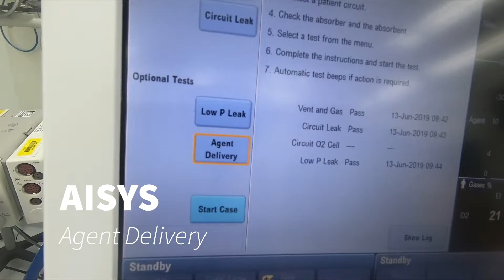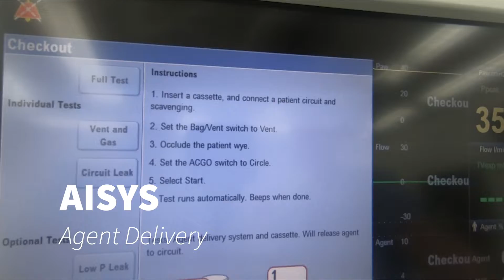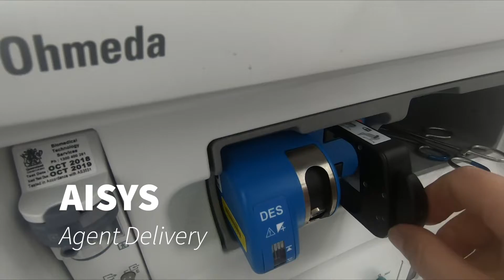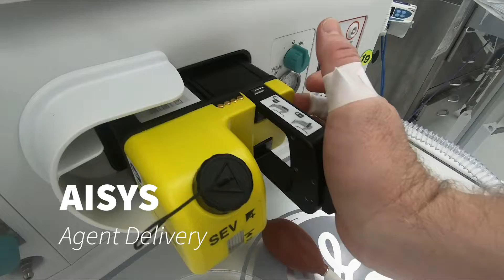So there's a few concerns there. Must make sure the scavenging is working. What is it here? Insert a cassette and connect the patient circuit and scavenging. So make sure it is the SEVO and not the DES. Just for people who don't know how to operate that, there's a locking mechanism there, and then the whole cassette comes out and you can press it back in. So you can use quite a bit of strength there.